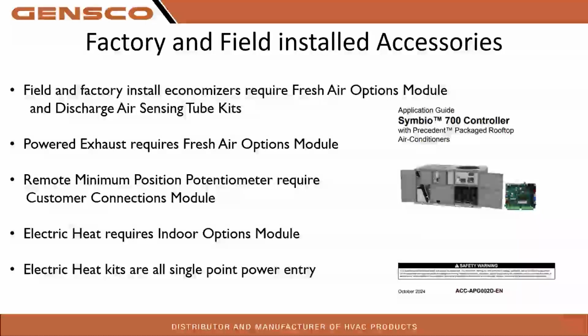When ordering equipment, the 410A, if you could still get any 410A package gear, you will not be able to add factory accessories like economizers and smoke detectors. If you're ordering the 454B, you can add your factory economizers, powered exhaust, minimum position potentiometer, electric heat kits, but most of the time we're seeing a lot of these field installed accessories, FIA, field installed accessories. So you need to know what you have in the system before you start working on it and programming the Symbio board.